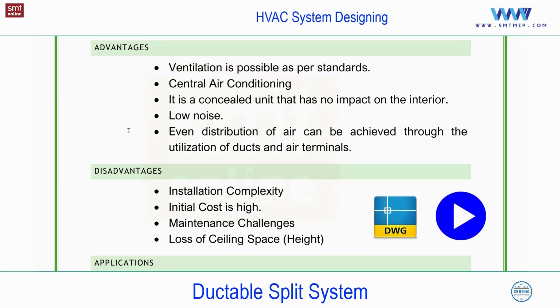Next, as I explained, ventilation as per the standard is possible, whatever standard you are following as per your consultant, in a central air conditioning system. And you see, it is a concealed unit, so it will not affect the interior because it is above the false ceiling, so it is not visible. Even some interiors will not accept even a high wall FCU, because that also will appear in the space, no? So as per the interior requirement, they may not accept that. So they ask for a cassette or concealed unit.